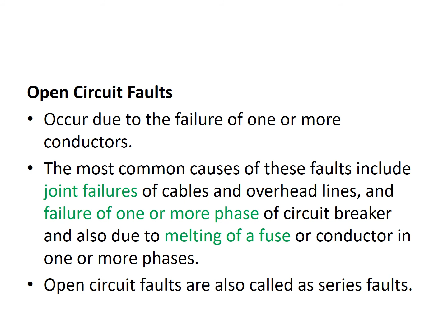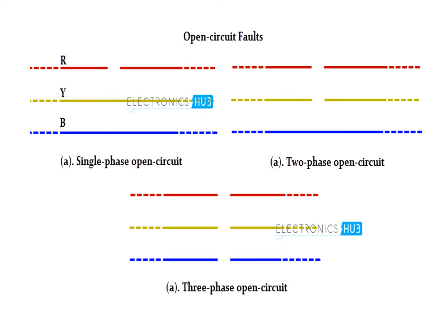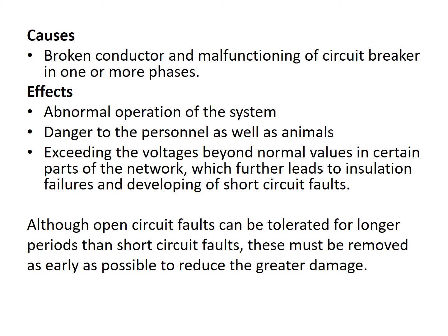Open circuit fault occurs due to the failure of one or more conductors. The conductors may break. One phase may break, two phases may break, or all three phases may be open. Causes may be broken conductors and malfunction of the circuit breaker in one or more phases. Effects are abnormal operation, and may be danger to personnel as well as animals.